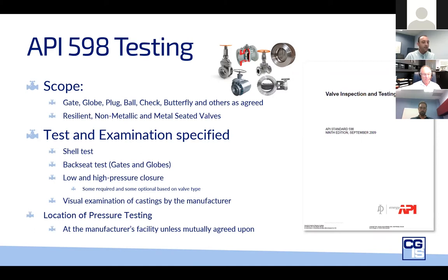The location of the testing is done at the manufacturer's facility and does not equate to the same performance once installed and operational. Valves require generally to be tested once they're in the field during commissioning. I came across one case recently where the valve was being tested during commissioning and they wanted to test it to 150% of the rated pressure using the isolation valve closed as a line stop. That showed a lack of understanding of what the valve is capable of — testing the closure member fully shut to 150% of maximum pressure could potentially blow out the seals or cause irreparable damage.